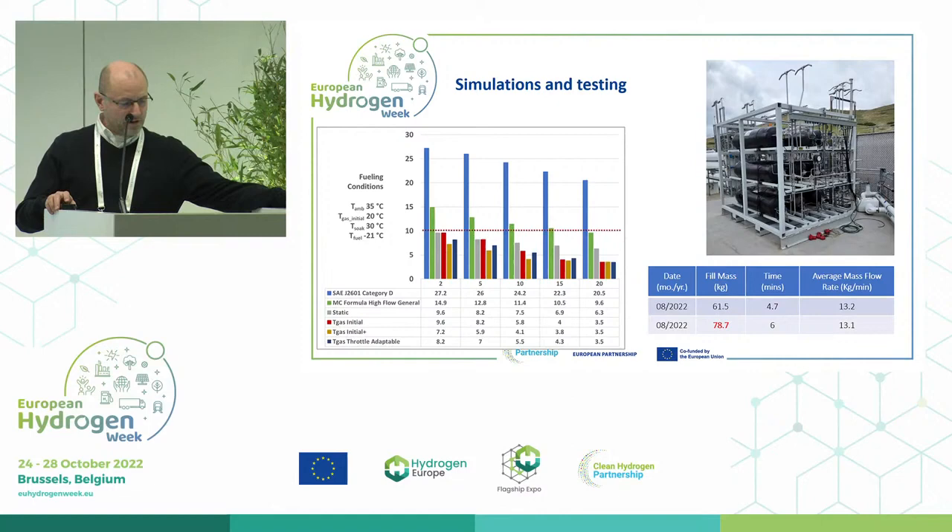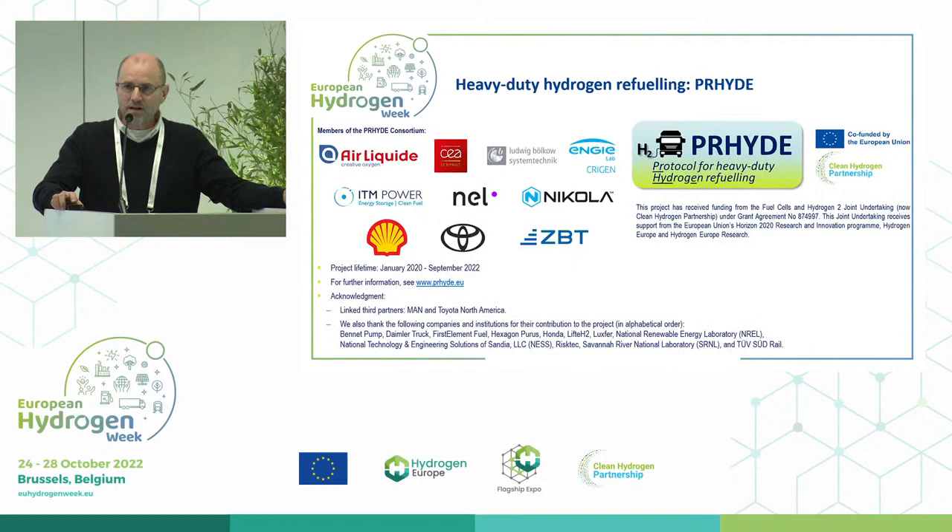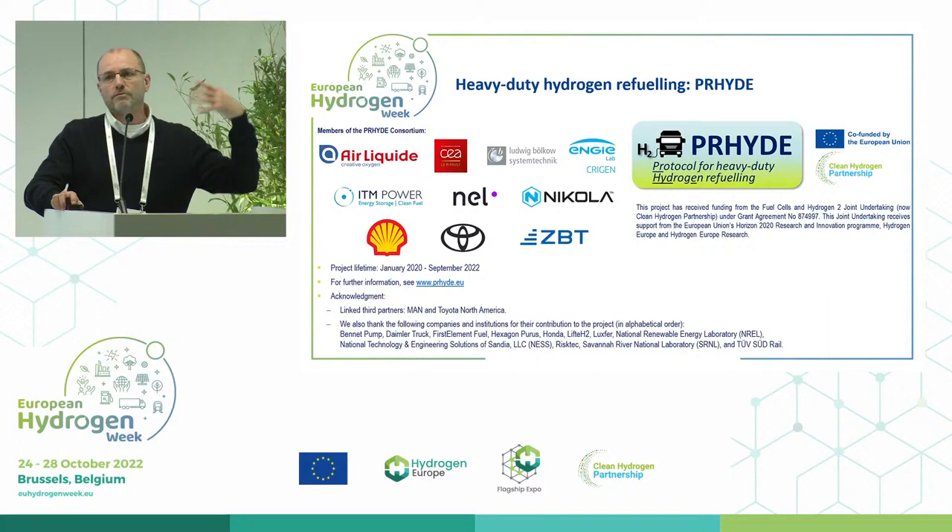Here are the results — this is the nicest slide. In the blue graph, which is the current D category of the SAE J2601, you can see the fueling performance. As soon as we go into the MC formula high flow general, which is the dash-5 version (the green one), it's double the speed. And as soon as we go into the four PRHYDE protocols — gray, red, yellow, blue — the speed goes super fast compared to the current protocol. We can compete with diesel fueling. This has been simulated at NREL and at ZBT in Germany in real-life conditions and via modeling.